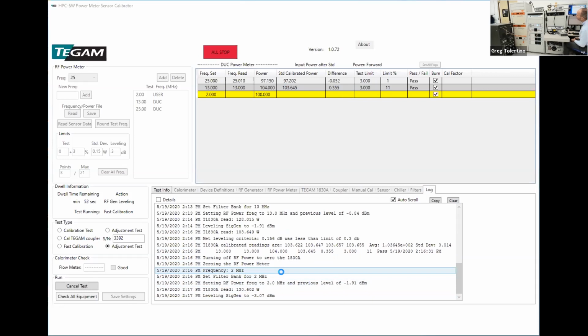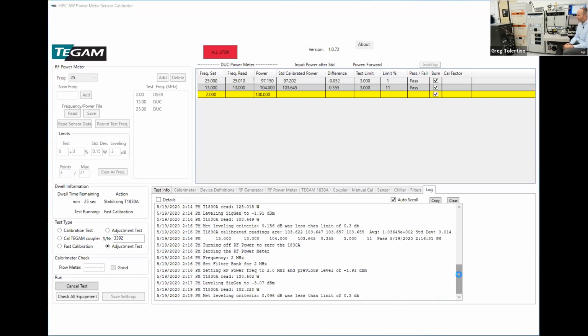We have about another minute to wait, and then it'll go ahead and use that point. The bandpass filter bank that I was talking about, with the 3 chassis of 8 filters apiece, we're doing bandpass filtering over a range of 100 kilohertz to 4.2 gigahertz, which is probably a wider range than most people's labs need. But our lab covers that range because we actually calibrate products over that whole range. Many other labs might only need 2 sets of 8 filters to cover their needed range. All right, we're leveled out at 2 megahertz now and about to get the point burned.